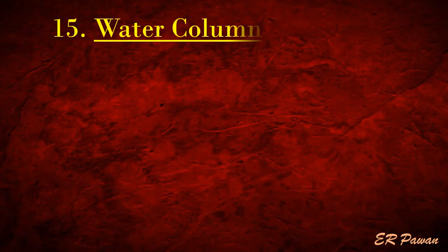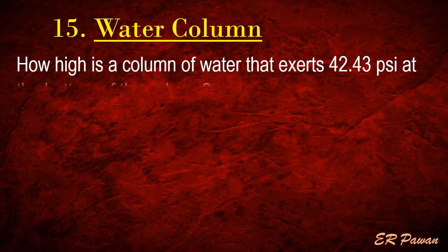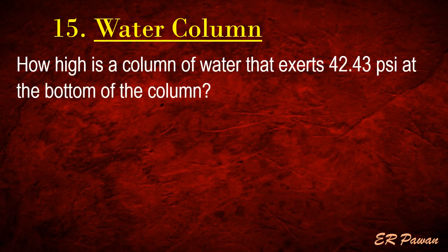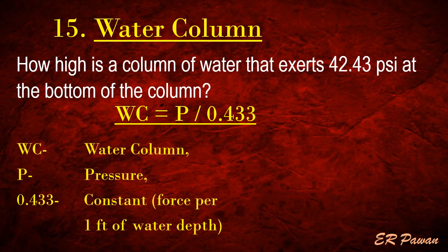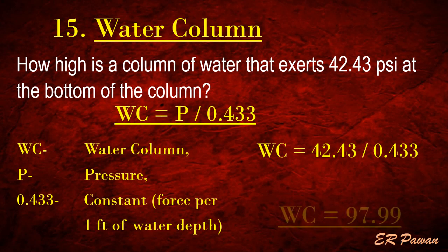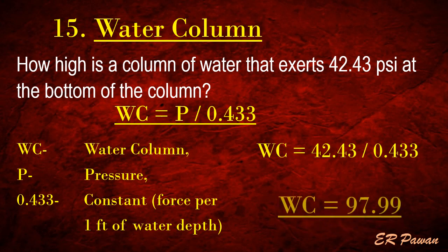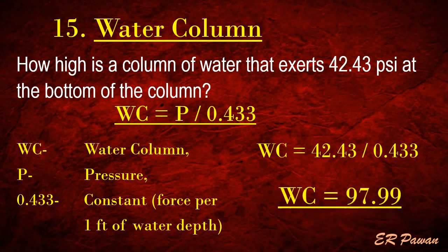Formula 15 — Water Column. How high is a column of water that exerts 42.43 pounds per square inch at the bottom of the column? Water column height equals pressure divided by 0.433, where 0.433 is a constant representing force per one foot of water depth. Let's put the value in the formula.